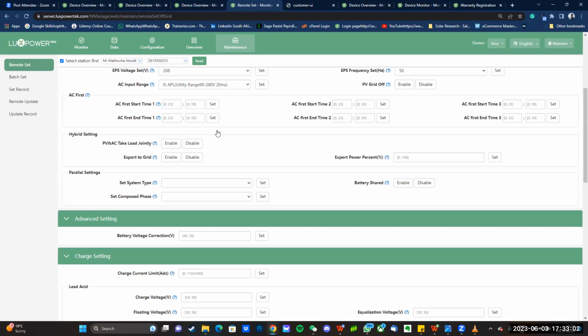So when you turn this on, there will always be a slight backfeed which you cannot control. If your client has a prepaid meter sensitive to rolling back, the moment it starts rolling back, it's going to trip constantly. In cases like that, you either need to change the prepaid meter to one that accepts rolling back, or contact the prepaid meter company to see if they can give you an access code allowing rolling back to a certain percentage. So there are ways of getting around that.